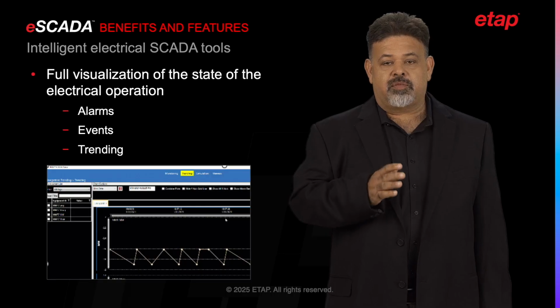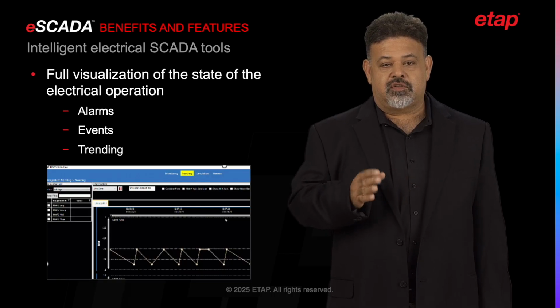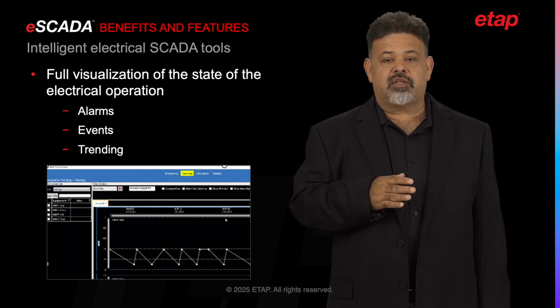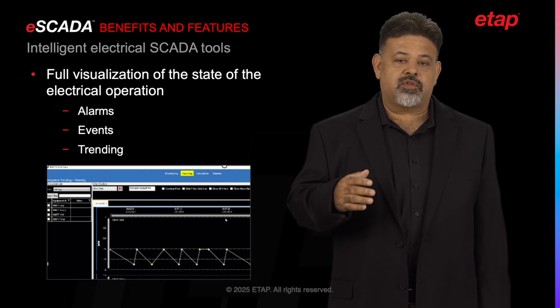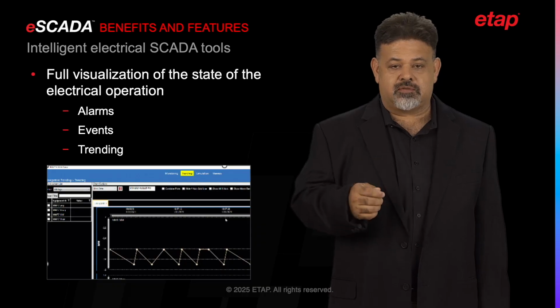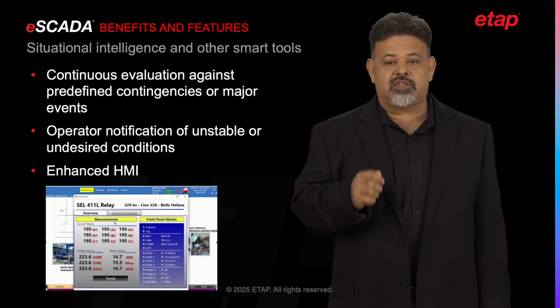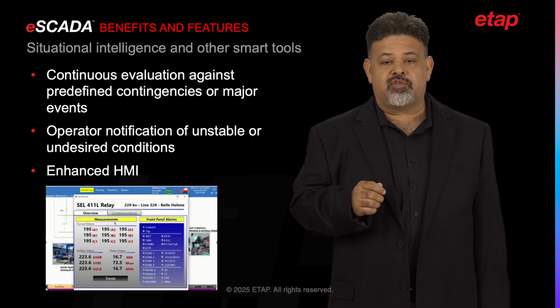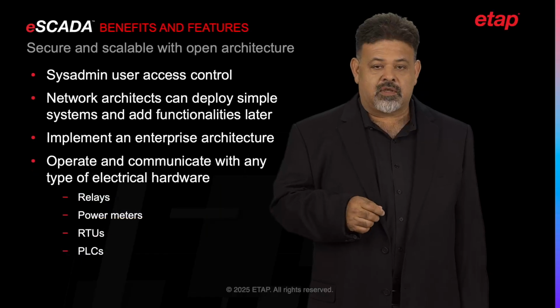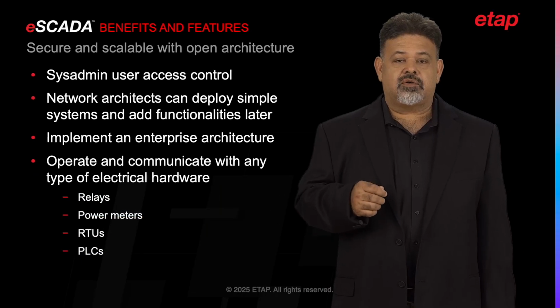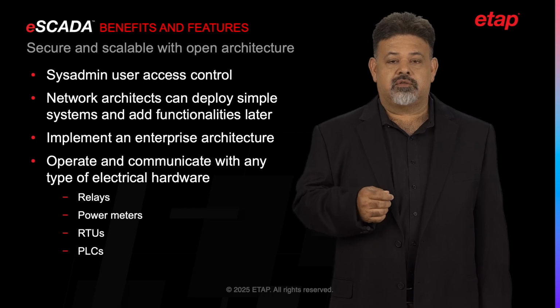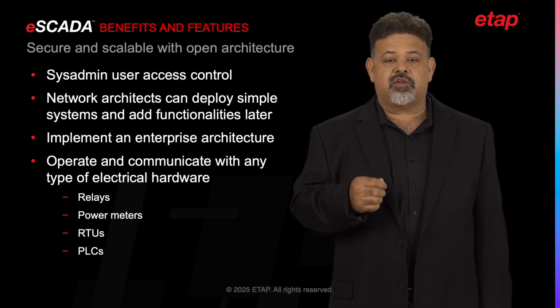Powerful monitoring is complemented with powerful SCADA tools. These tools, such as alarms, events, trending, and more, provide engineers and operators with full visualization of the state of the electrical operation. Smart tools such as situational intelligence continuously evaluate the system against predefined contingencies or major events and notify operators in the case where an operator procedure or action may result in unstable or undesired conditions. ETAP eSCADA solution is a secure and scalable solution with an open architecture. Its secure environment allows system administrators to limit users to specific features and actions.